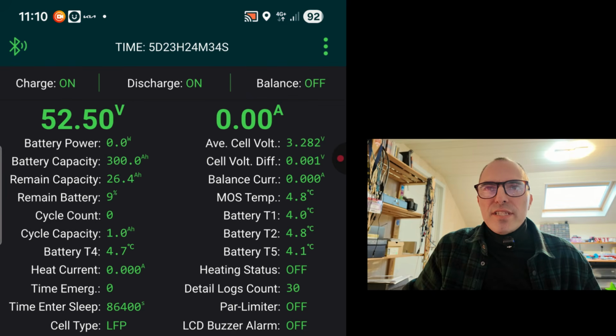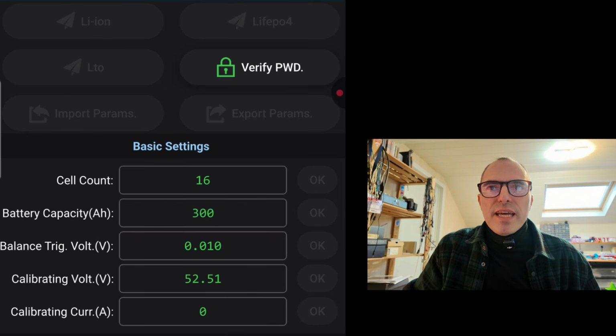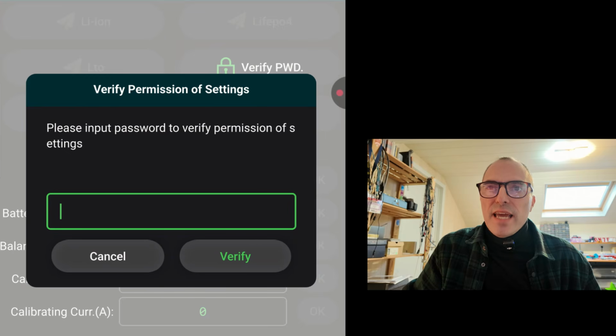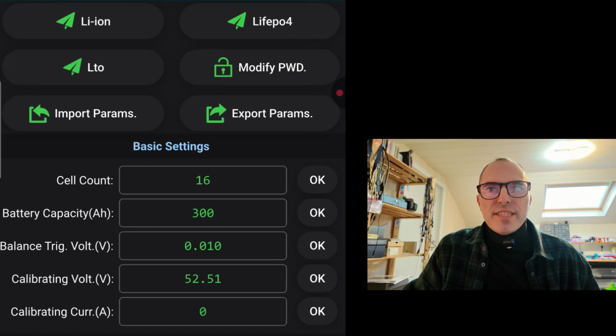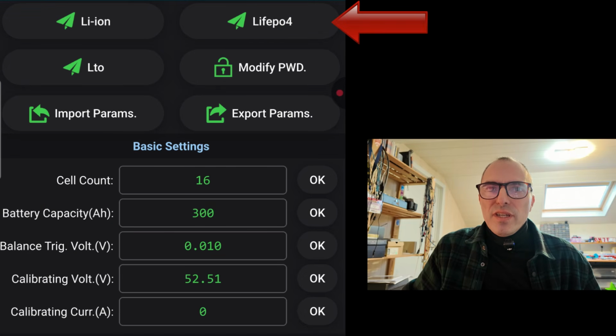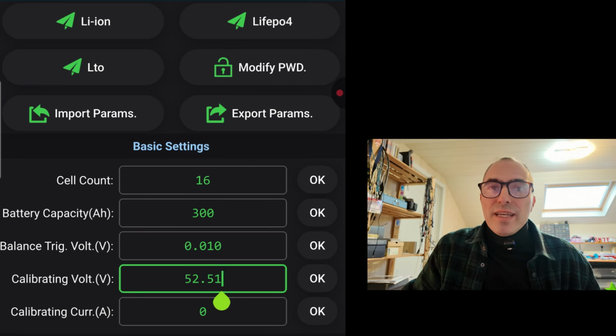When you start with the BMS, the first step you have to do is set technology, number of cells and the capacity of each cell. To change these settings and to enter the advanced settings menu, you have to enter the standard password 123456. A very important note, if you change the technology, all advanced parameters will be changed to the standard parameters of that technology. That means you have to re-enter all parameters, so be aware of that.